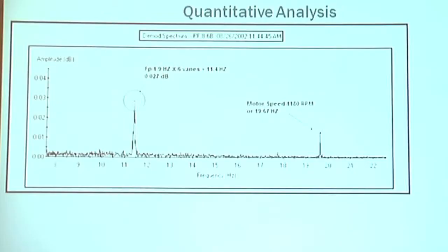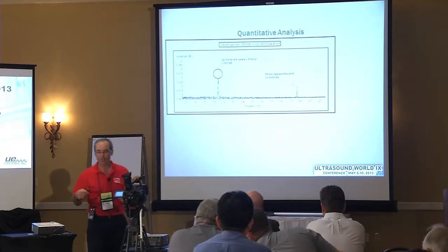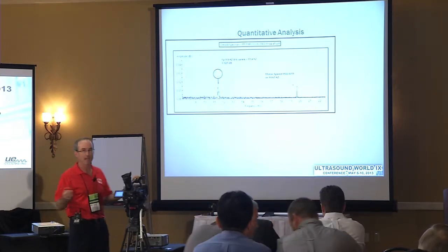Another quantitative example right here, this is for, I don't remember what this actually was. I'm pretty sure it was a pump, there were vanes, so it's either a pump or a fan, but probably a pump in this situation. There are two specific frequencies: the motor speed and the vane pass frequency. Again, a mechanical peak that shows up on your current.